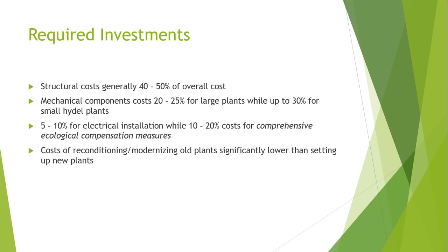For small hydropower plants, roughly 5 to 10 percent has to be set aside for the electrical installation. What remains are the miscellaneous costs, which include the planning costs, additional construction expenses, overheads, and the building interest rates — that is, the interest payments on the invested capital during the building period.